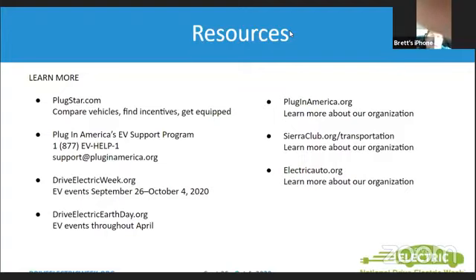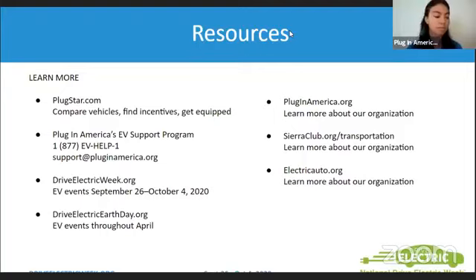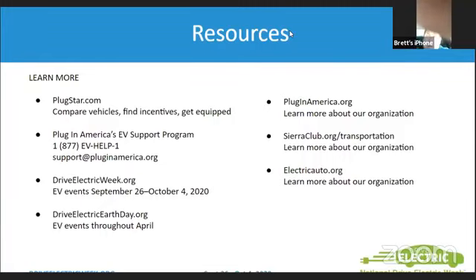Historically here in Southern California, 100 amp panels are very common. Most of the time that is a smaller panel than what is needed to support most charging stations, so we'll work with utility companies to do an upgrade for that panel. Commonly a 200 amp panel is usually large enough for us to successfully install a charging station. But when we start getting down into 100 amps and below, especially with apartments and condominiums having smaller main panels, it becomes even more difficult. I hope that answers your question.